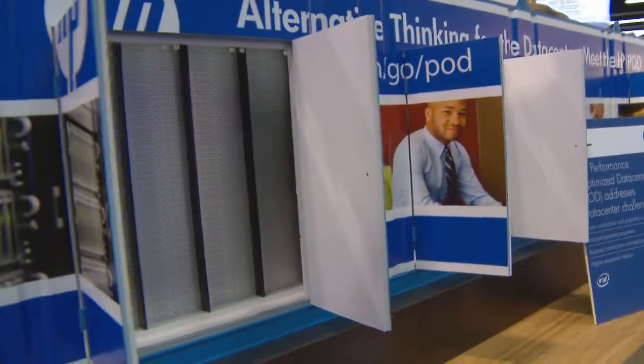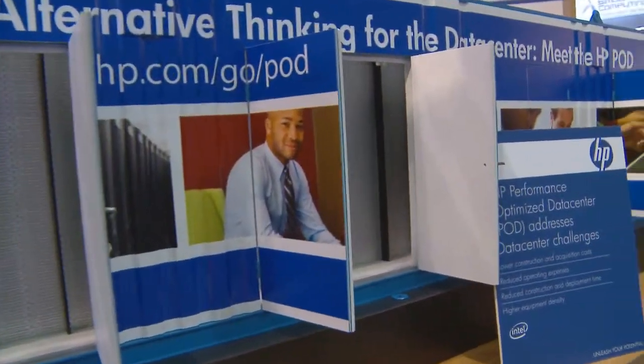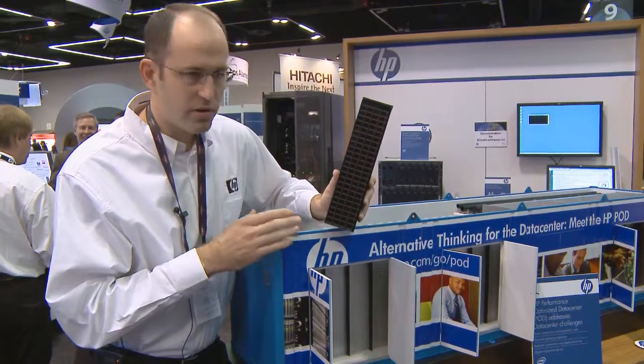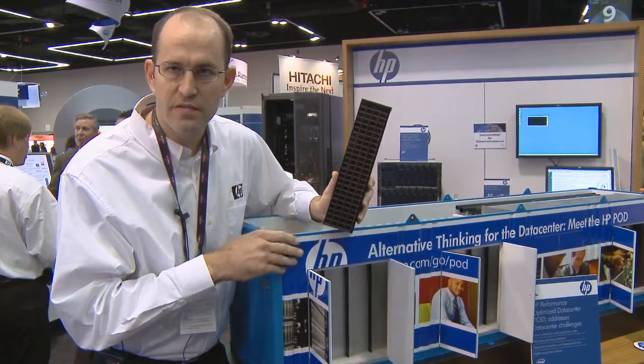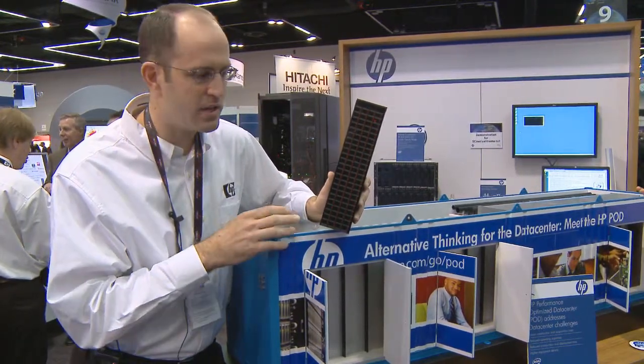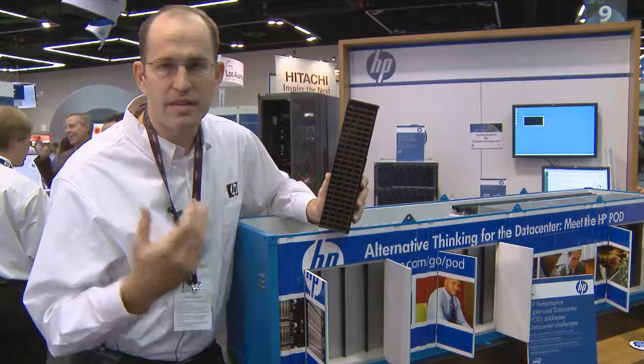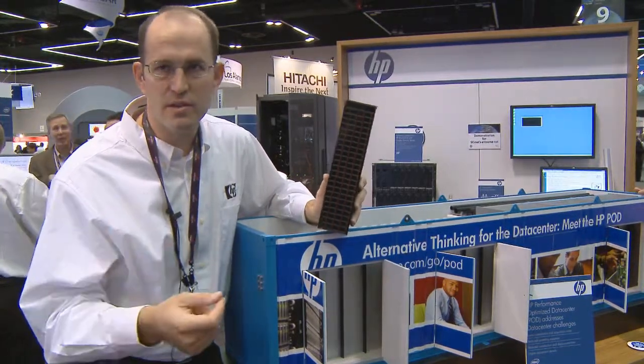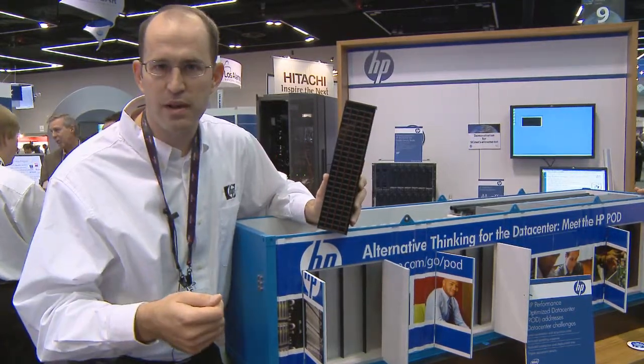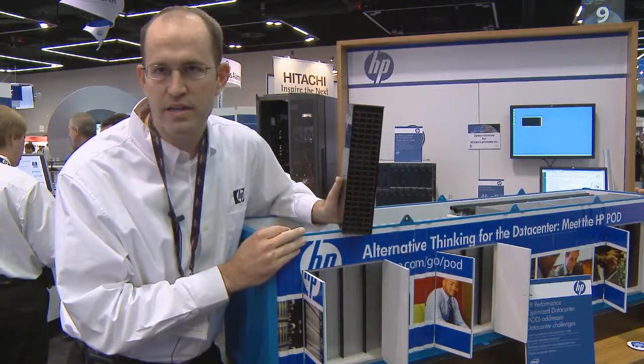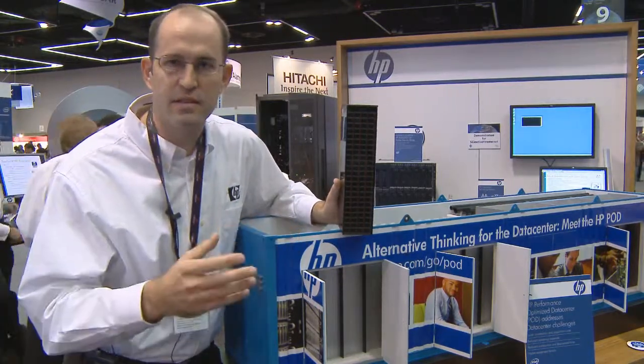Additionally, because we build this in the factory using the perfect process and the perfect tools, you're typically going to see a CapEx savings of 15 to 25% by using the HP pod. Not only that, from a technical perspective, we can go up to 600 kilowatts, 27 kilowatts per rack, so this blows a conventional data center out of the water in terms of the density of equipment it can support.